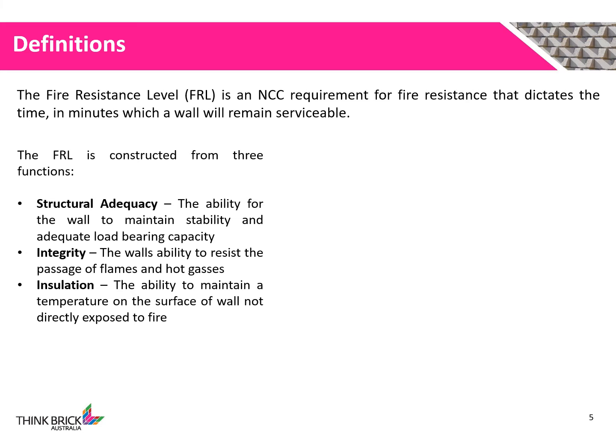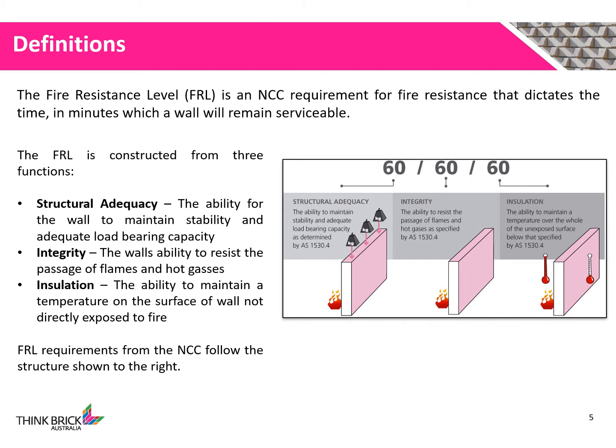Structural adequacy is the ability for the wall to maintain stability and adequate load bearing capacity. Integrity is the wall's ability to resist the passage of flames and hot gases. Insulation is the ability to maintain a temperature on the surface of the wall not directly exposed to fire. Generally, FRLs are presented using the notation provided in the figure to the right.